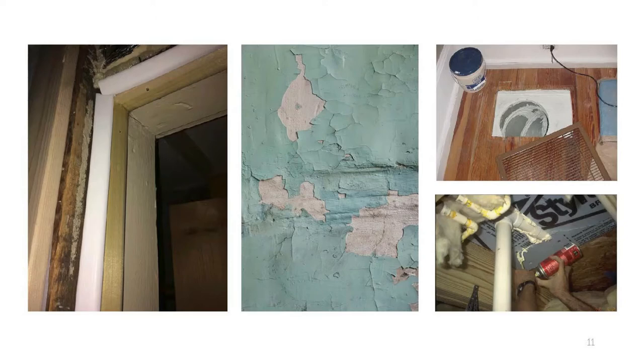Pressure barriers are complex and must be based in building science. Examples include maintaining a positive pressure in one location with respect to another location in the home or building that cannot be fully isolated from the occupants due to complexity in air sealing or other issues. For example, maintaining a positive pressure in the living space with respect to a damp crawl space. Pressure barriers are often combined with ventilation to ensure performance and can be energy intensive.